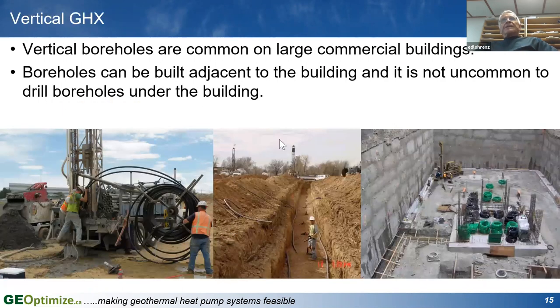So different ways can be used to get pipe into the ground. Vertical boreholes, especially in larger commercial buildings, is probably the more common, simply because it takes less space to build it. In some places they've installed the pipes in piles underneath the building. We're working on a project right now in New York City where they've got 190 some odd piles that are 120 feet deep. The pipe in those piles will supply about 30-35% of the heating and cooling energy for that building.